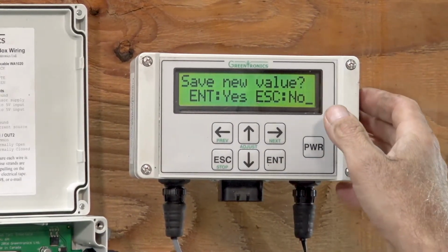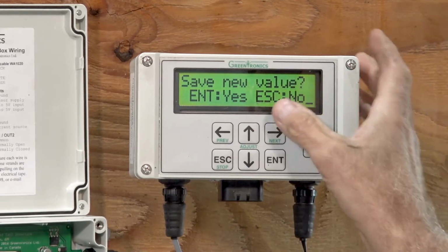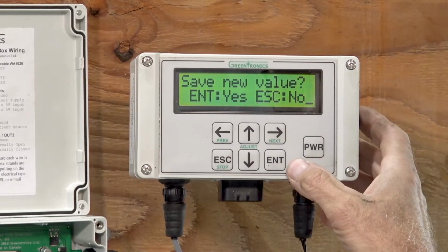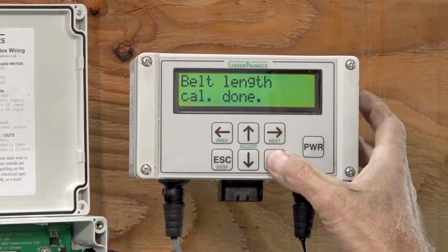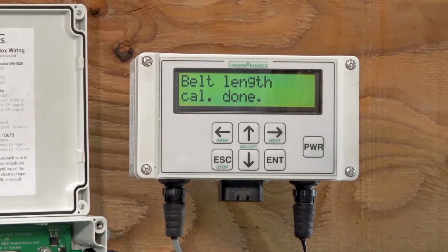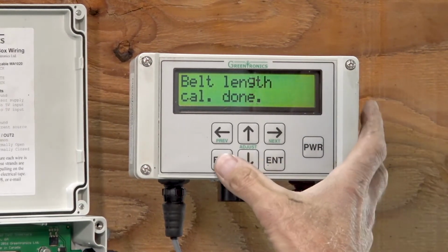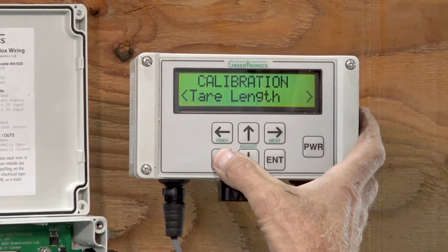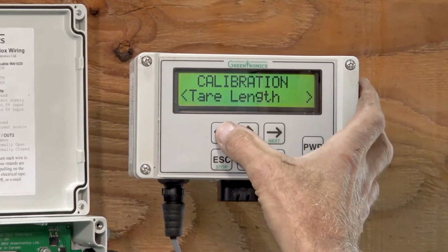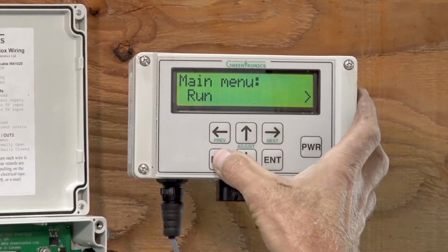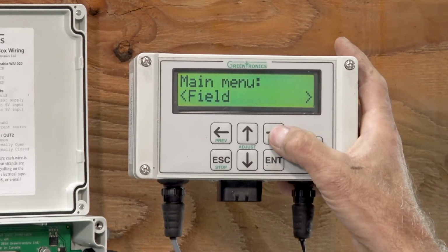So Andy gave me the signal, I hit escape. Now it asks me, do we want to save the new value? And I click enter for yes. And the belt calibration or tare length calibration is finished. So we can escape out of here and we can go right away to our tare calibration, which let me go back to run so I can show you where that is.